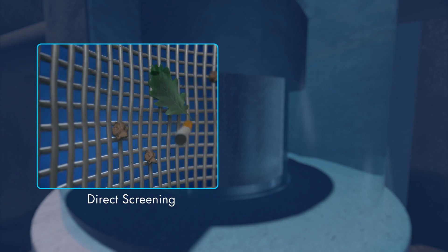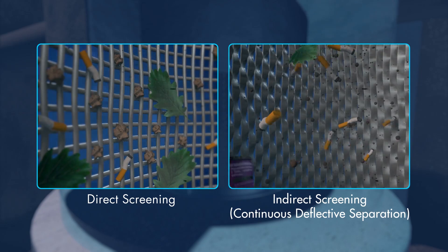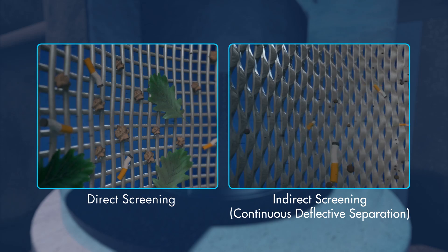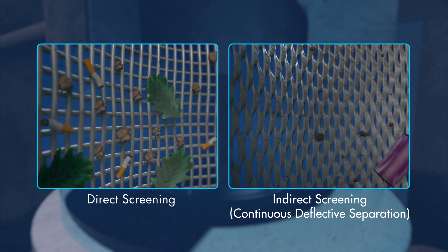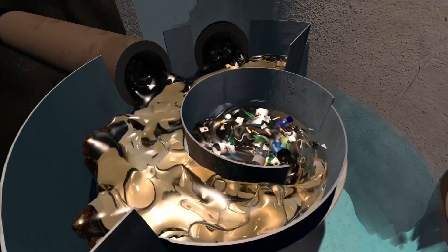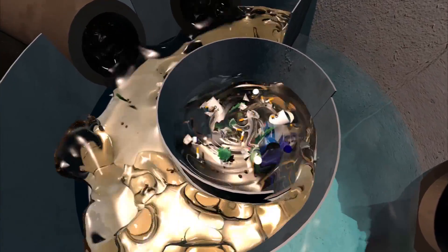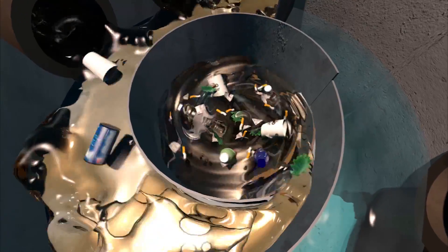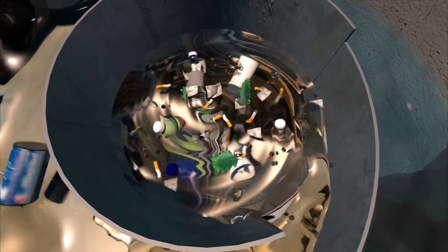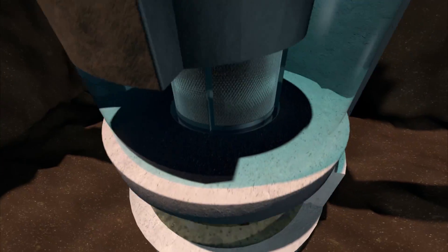Unlike traditional screens that can easily become clogged, water velocities within the swirl chamber continually deflect debris off the specially designed screen to keep it clean. The combination of swirl concentration and indirect screening forces floatables and solids to the center of the separation chamber. 100% of floatables and neutrally buoyant debris larger than the screen aperture are trapped in the chamber, and sediment settles into an isolated sump.